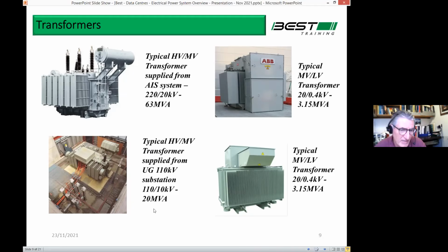The one down below is another data center I worked on. This is out in Clonshock, and this is 110 kV down to 10 kV. So it's a smaller transformer. This one is 20 megawatts. The one above it is 63 megawatts. That's a typical one that's fed from an underground supply from the ESB, a remote ESB substation. So it's a different arrangement. They're HV to MV transformers.